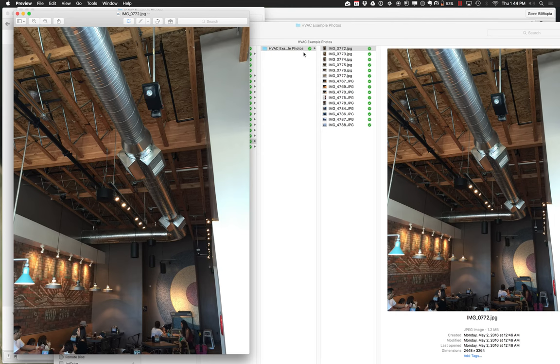As the duct runs along, you can see it has transitions where it gets a little narrower as it goes. The reason is that after every pair of air caps drops off air, there's less volume flowing downstream, so the duct gets smaller to match the reduced airflow. Those are just simple things to observe.